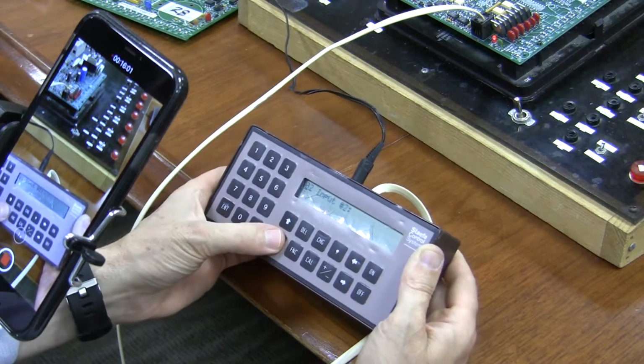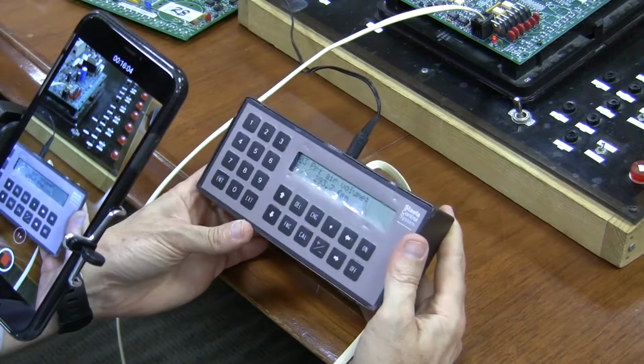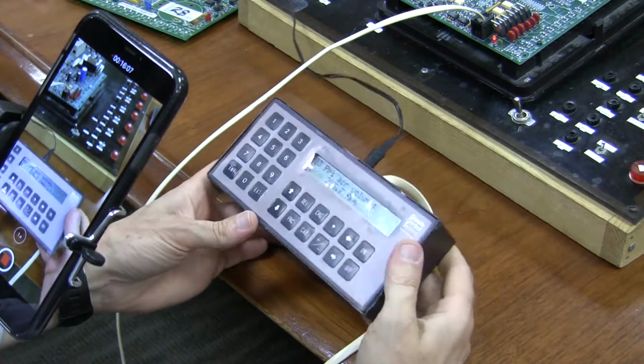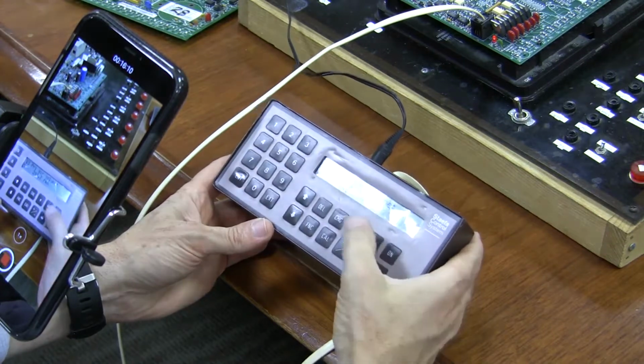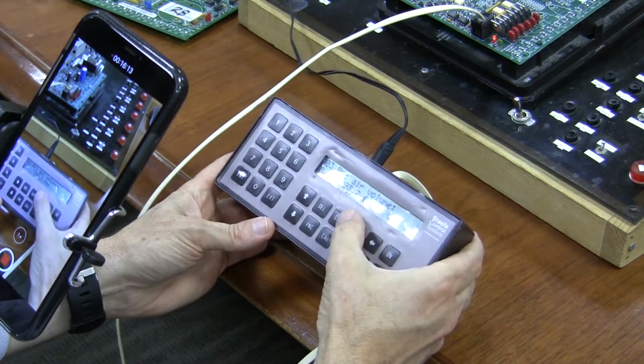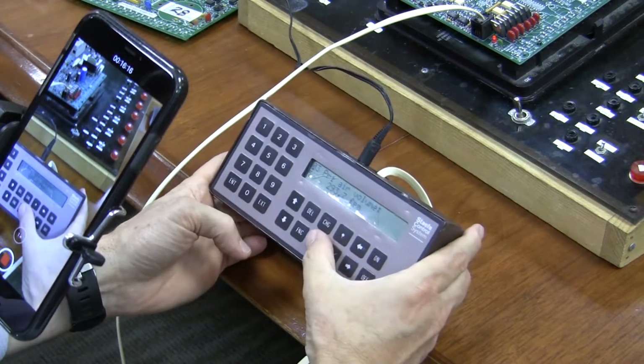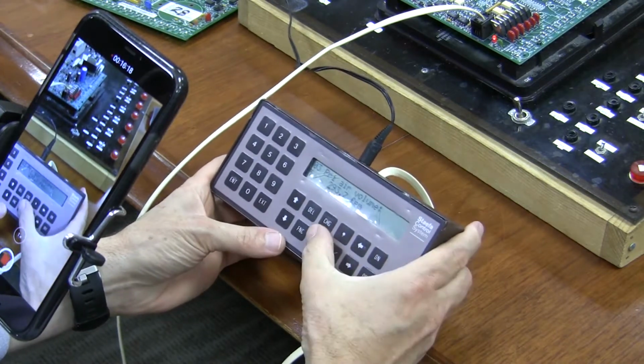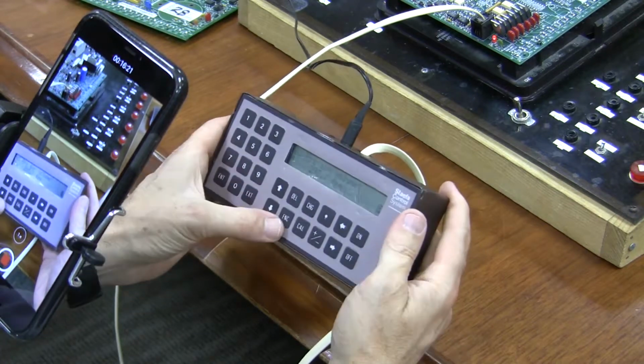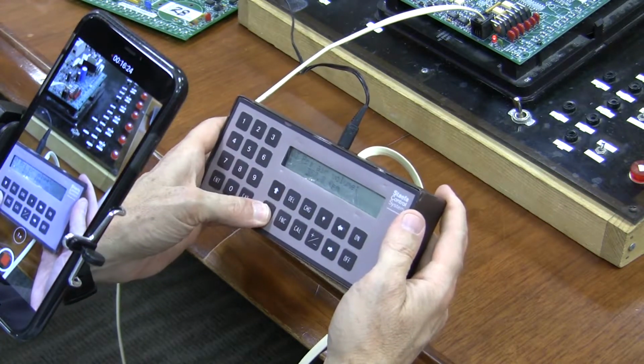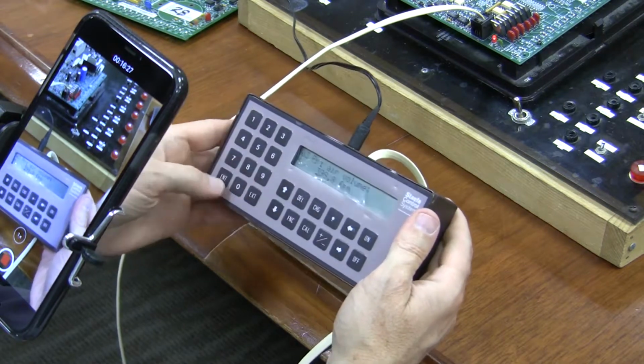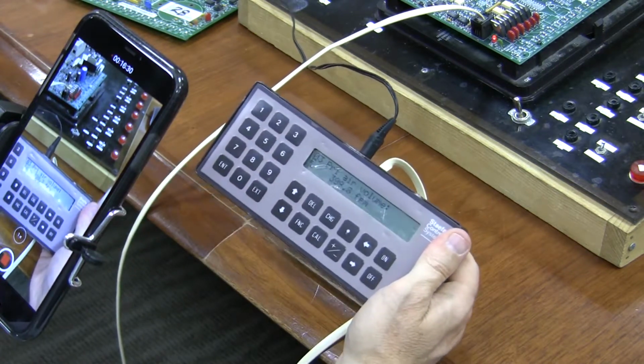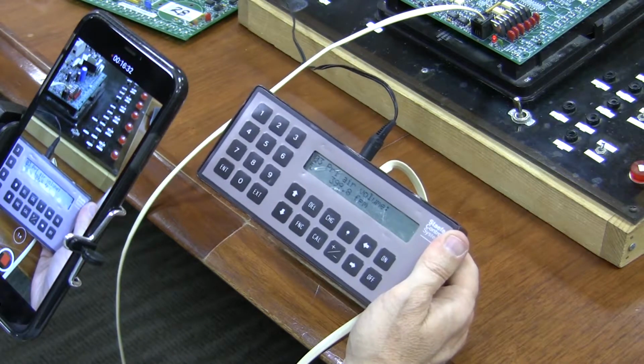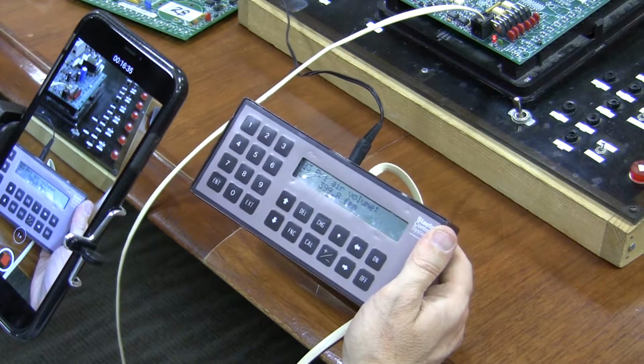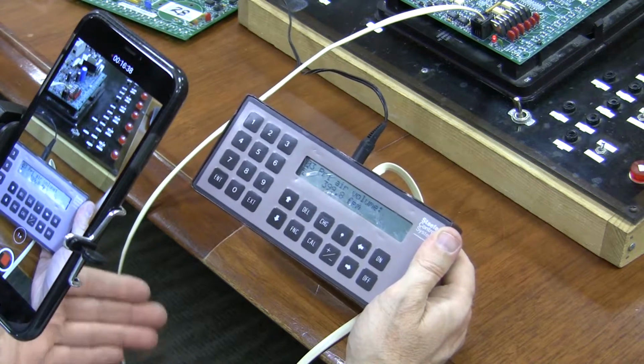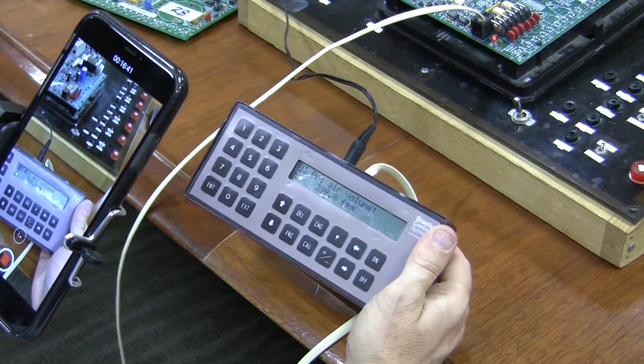He goes to input 3, he measures the flow. In this particular case, we're saying it thinks it's got 293 CFM there. And we are going to calibrate it, because notice it's got a little calibrate thing there. We're really, oh, I think I hit function set. So I'm going to hit calibrate. And I'm going to tell it, you're not really 300, you're about 400 CFM. And that's how the balancer calibrates it. Right? He measures all the grills in the room. And he says, I got this flow, but the actual service tool is reading this other flow. So he comes in and he calibrates.